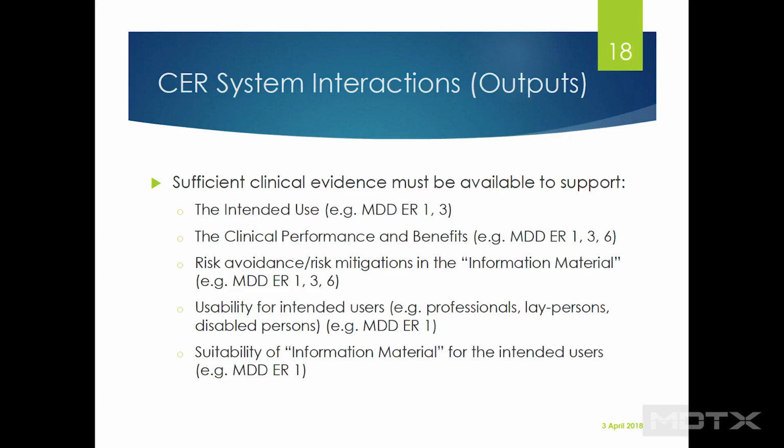So these are citations from the MDD. I actually don't have the citations from the MDR in here. She has them. Okay, but remember, right at the moment, if you're doing CER updates right now, you are still under the MDD. You can go forward to the MDR. You can choose to, but this is a regulatory strategy decision, right? You can also choose to meet the MDD at the moment. If you're putting a lot of money and effort into doing CERs right now and then transitioning to the MDR, it's probably not a very wise strategy to spend much time and money meeting those, but you can. You can for now. And that's an advice question I would definitely be asking Anne later on.